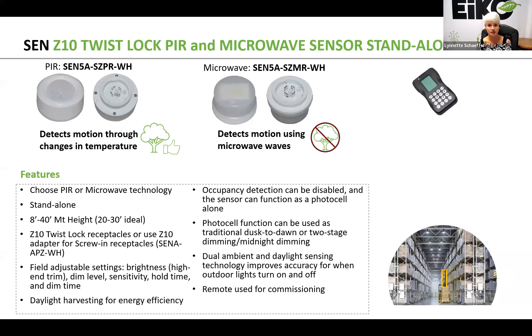You can also enable the daylight sensor. These do feature daylight harvesting, which is a great feature for indoor applications where natural daylight is present. Although both have occupancy detection, this feature can be disabled and the sensor can function as just a photo cell alone for dusk-to-dawn type applications.